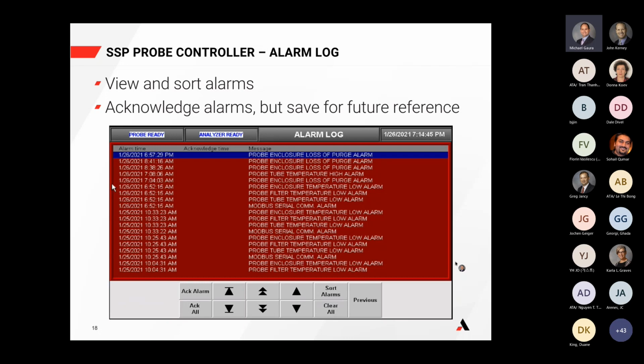Okay, so as I mentioned, the next screen we're looking at will be the alarm log screen. In here, nobody panic. This is some factory testing that was going on, and we were able to generate a number of different alarms here. Some of them are just normal during a startup, where you can see the filter temperature is a little bit low and the enclosure temperature is low. And again, we were generating alarms because once we're sampling, we want to make sure that those components are staying near their set points. And if not, we generate alarms that are viewable to the end user, and we can output alarms from the controller as well.